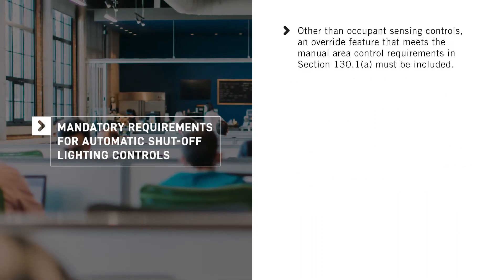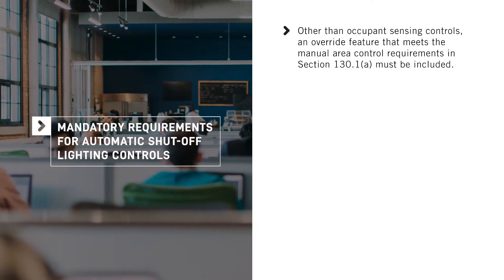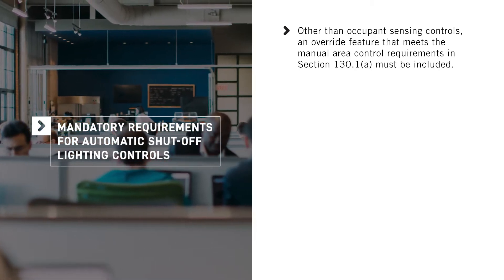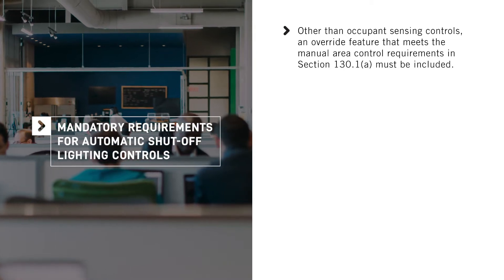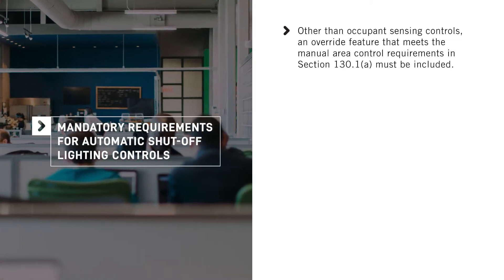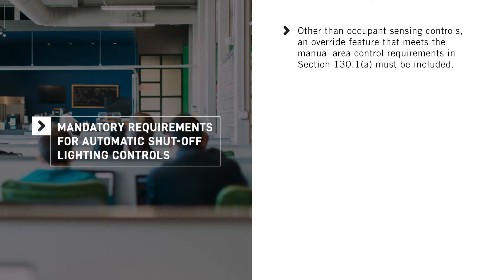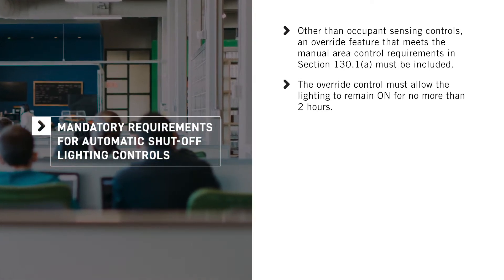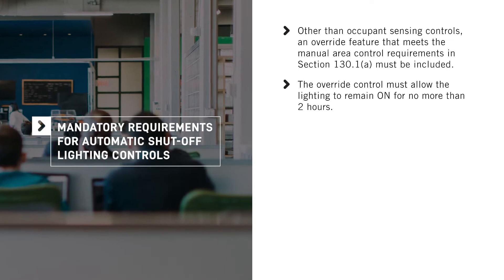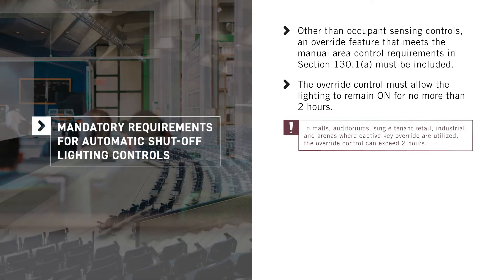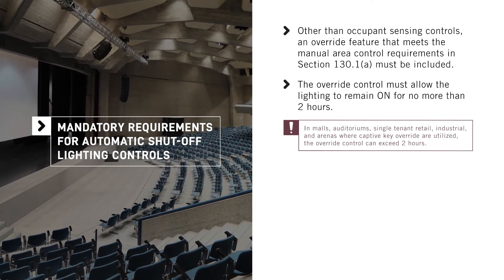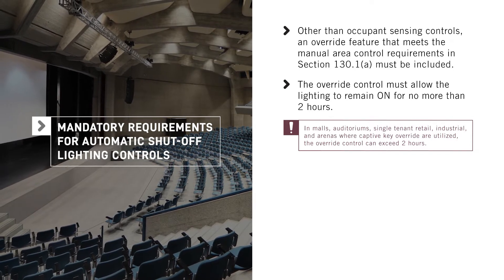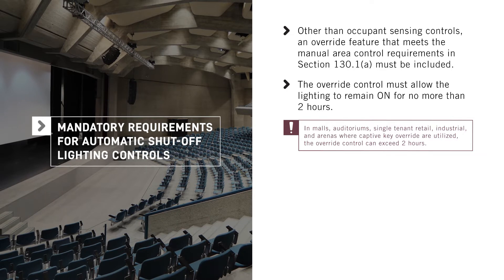Automatic time switch controls, other than occupant sensing controls, must include an override feature that meets the manual area control requirements in Section 130.1a so that occupants can manually control the lighting. The override control must allow the lighting to remain on for no more than two hours. However, in malls, auditoriums, single-tenant retail, industrial, or arenas where a captive key override is utilized, the override can exceed two hours.